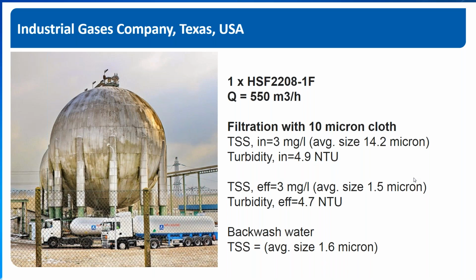and this is a trolley solution, which is our standard, which has an embedded sequence in the control system to do a chemical clean. Based on our experience, we can recommend certain chemicals to restore the capacity of the filter cloth. In terms of cooling tower side stream filtration, what we typically see is that the conditioning of the water in the cooling tower is typically good enough to maintain a good capacity in the filter cloth, in the filter.